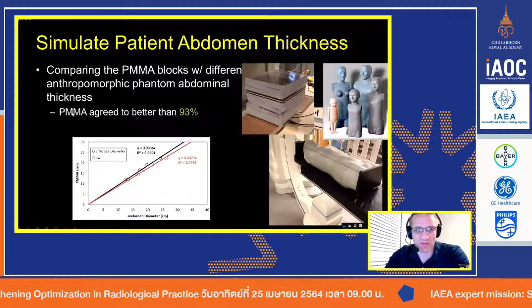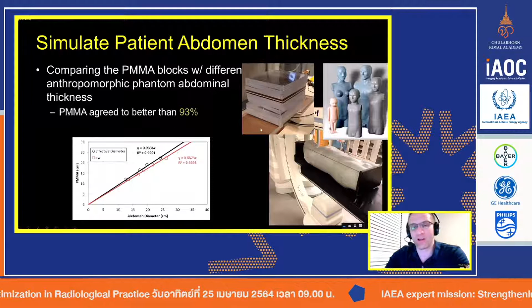And what you can see here is it's almost a one-to-one relationship. You can see here the PMMA agrees with these blocks to better than 93%. So the fitting coefficient, the regression, is 0.999, so it's an excellent fit. And the conversion factor from PMMA blocks to these anthropomorphic phantoms is 0.9336, or roughly 93%. So the point here is these blocks are phenomenal if you want to use them to do dose and image quality optimization in fluoroscopy. All right, so getting to today's topic, dose metrics for fluoroscopy.